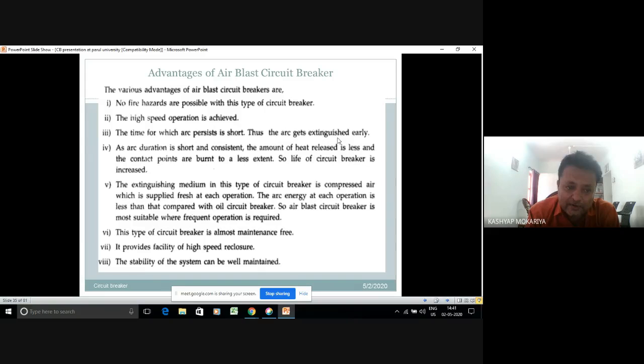So the air blast circuit breaker is most suitable where frequent operation is required. This type of circuit breaker is almost maintenance free. It provides the facility of high speed reclosing that I already discussed, and the stability of the system can be well maintained through this air blast circuit breaker.